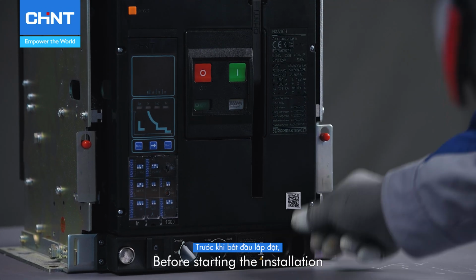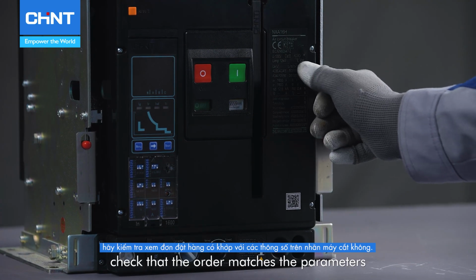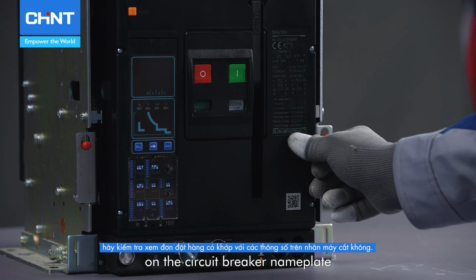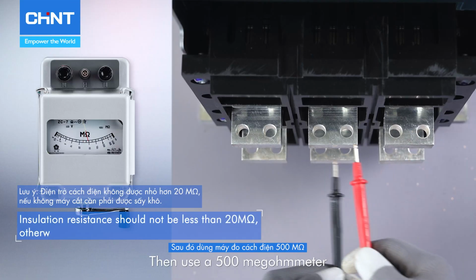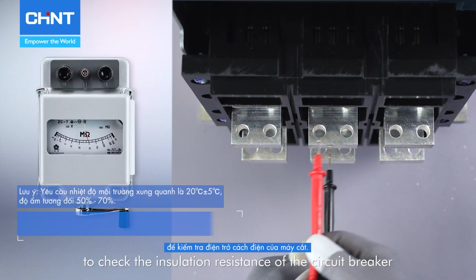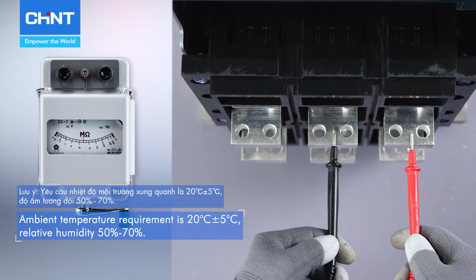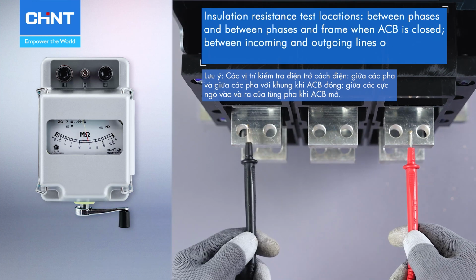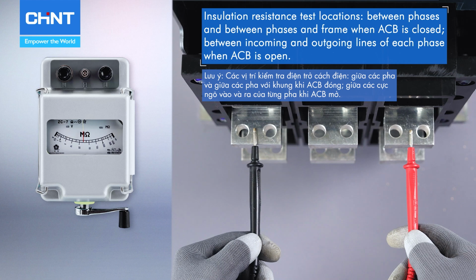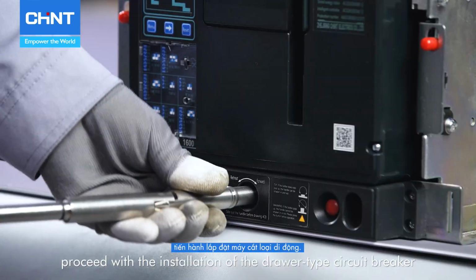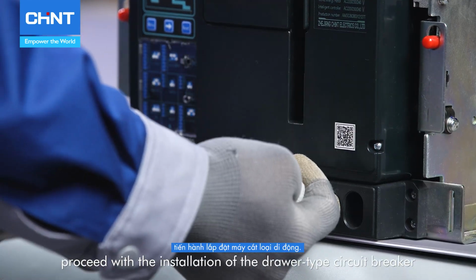Before starting the installation, check that the order matches the parameters on the circuit breaker nameplate. Then use a 500 megohmmeter to check the insulation resistance of the circuit breaker. Next, proceed with the installation of the drawer-type circuit breaker.